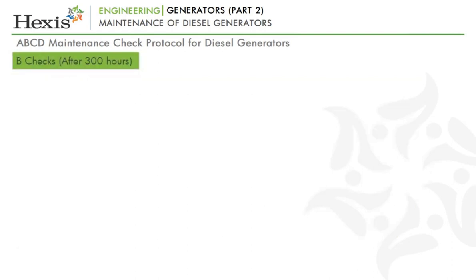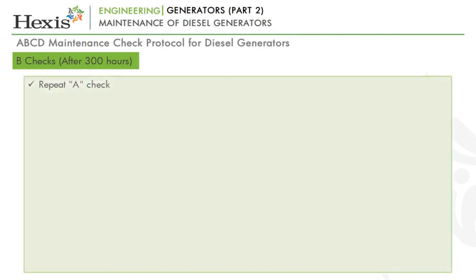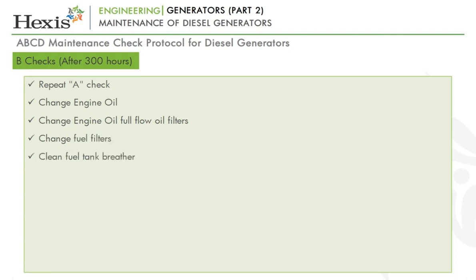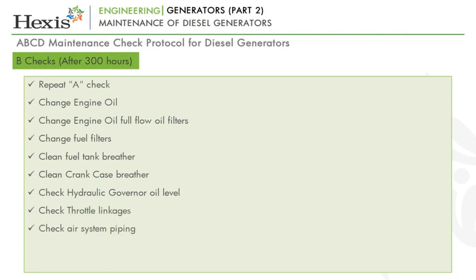Let's look at the B checks which are conducted after 300 hours of DG operation. Repeat A check. Change engine oil. Change engine full flow oil filters. Change fuel filters. Clean fuel tank breather. Clean crankcase breather. Check hydraulic governor oil level. Check throttle linkages. Check air system piping. Check vacuum indicator in air system.